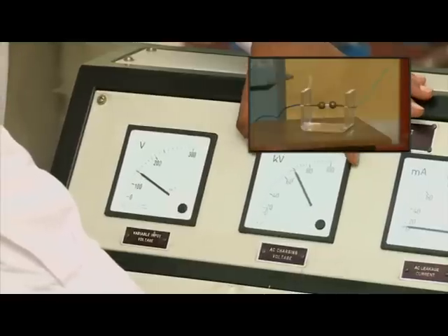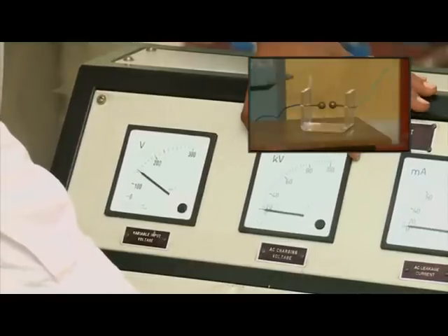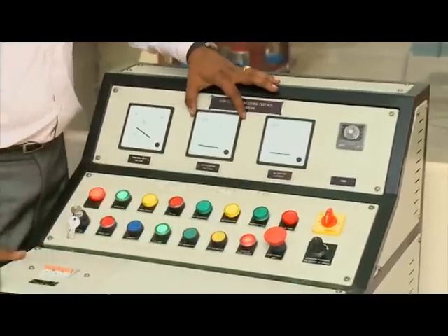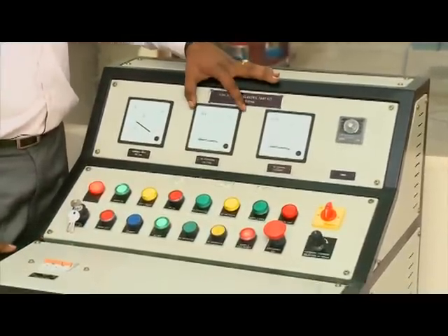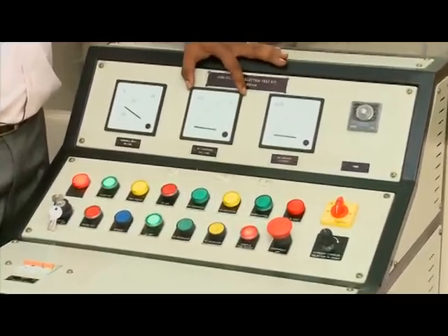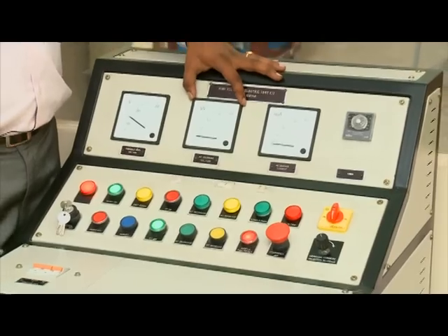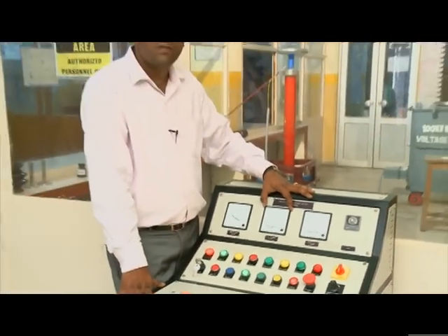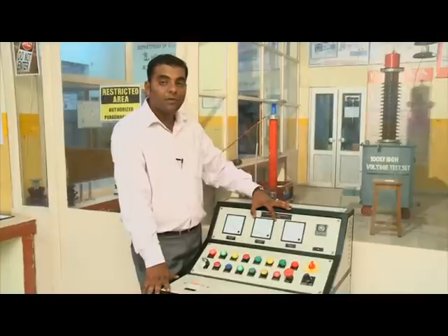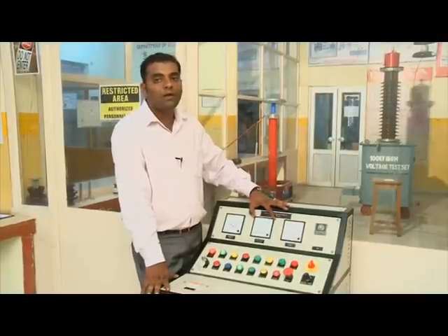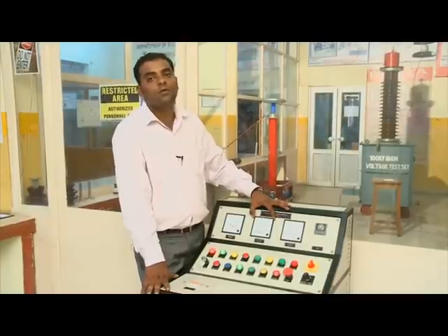On that particular value of output voltage, the value is 64 kilovolt. On that value of output voltage, the breakdown of air will occur. When the breakdown of air occurs, that voltage value will be the spark over voltage of the insulator string. We will substitute this value in the formula and calculate the efficiency of the insulator string.